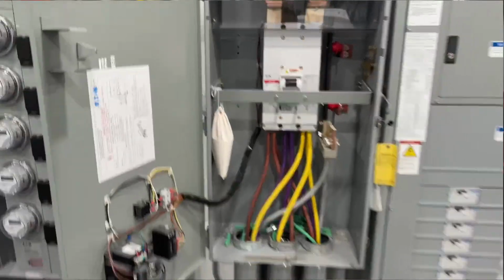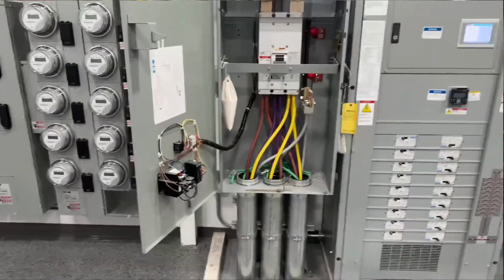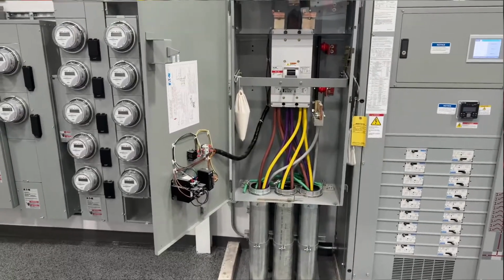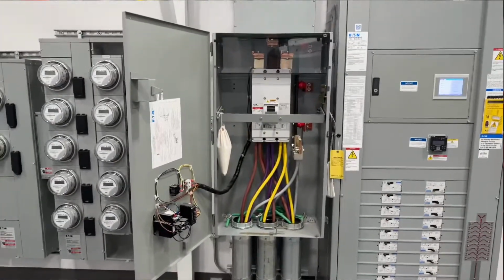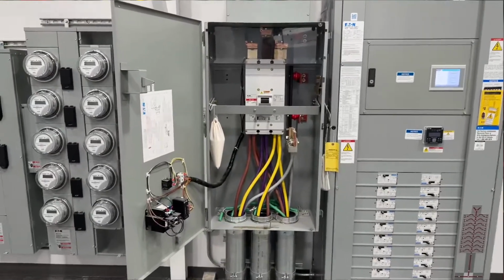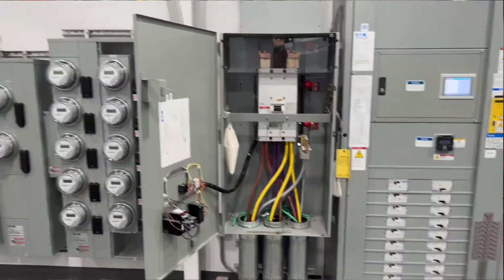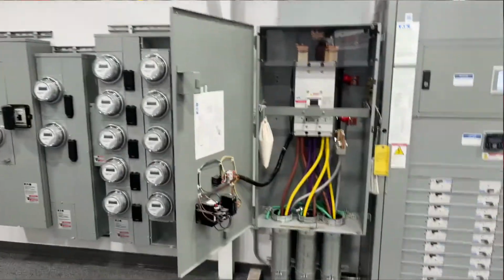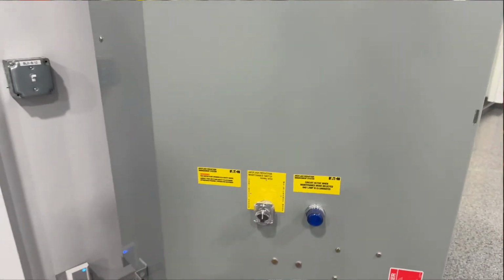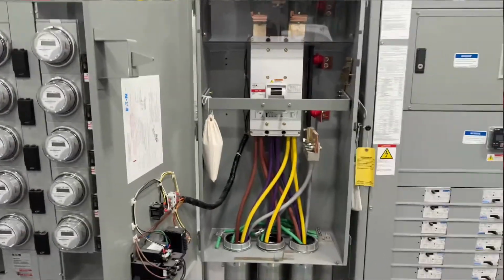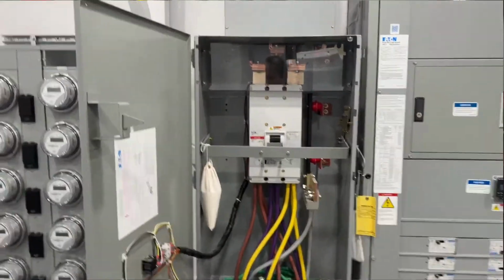This is a circuit. You see that one? Yeah, go ahead. This is an enclosed circuit breaker that has a switch built in. Look at that. Now that would be a good example of a circuit breaker used as a switch. It can also provide overcurrent protection for that switch as well, or for the conductors. It could be a service disconnecting means. Does that say service disconnect, John? Do you know? No, it does not. So it's not a service disconnecting. And it can also have a remote shunt. It can have a shunt trip if we wanted to do that.